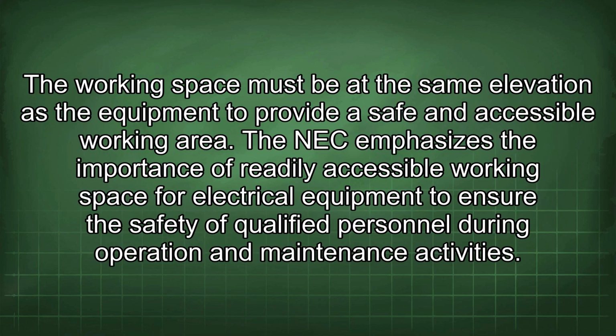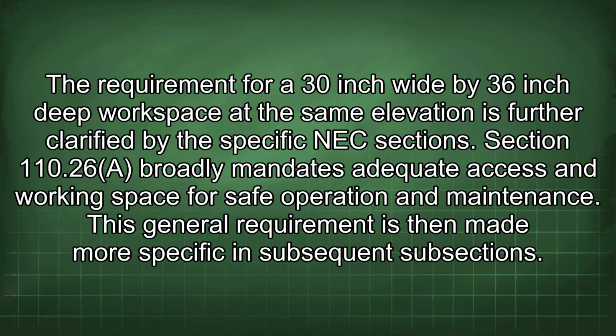The working space must be at the same elevation as the equipment to provide a safe and accessible working area. The NEC emphasizes the importance of readily accessible working space for electrical equipment to ensure the safety of qualified personnel during operation and maintenance activities. The requirement for a 30-inch wide by 36-inch deep workspace at the same elevation is further clarified by the specific NEC sections. Section 110.26 broadly mandates adequate access and working space for safe operation and maintenance. This general requirement is then made more specific in subsequent subsections.